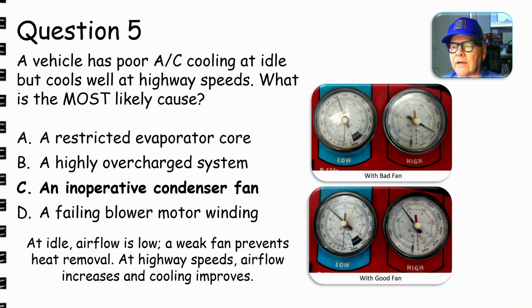Now the way that I troubleshoot that is with the thing running there in the service bay, I took a good strong shop fan blowing straight into the grill, putting air across the condenser just like you were driving down the road. If I see the pressures come down to normal, and it stops squealing the belt and getting the head pressure too high, then I know it's going to need a fan.